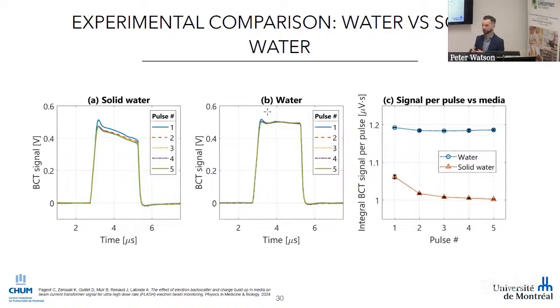Here we're showing an irradiation of 5 pulses in a row. For solid water, we have a decrease after the first 2 pulses, and then it stabilizes after the third one. While for water, the signal is rather stable. This decrease in signal, we've seen it for a while, and we thought it was the machine, the output of the machine decreasing as it was giving pulses. But when we irradiate water, we don't see that. So it's really an artifact of the BCT. It's not something physical from the machine.